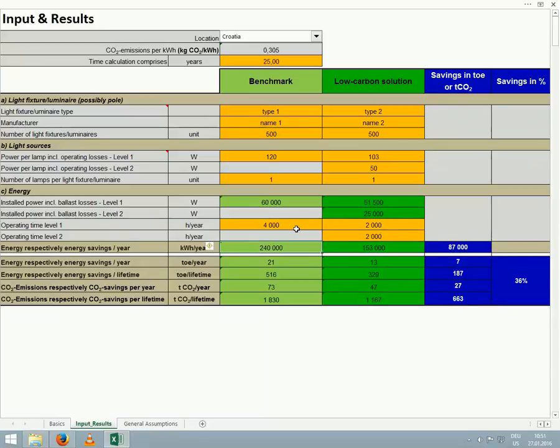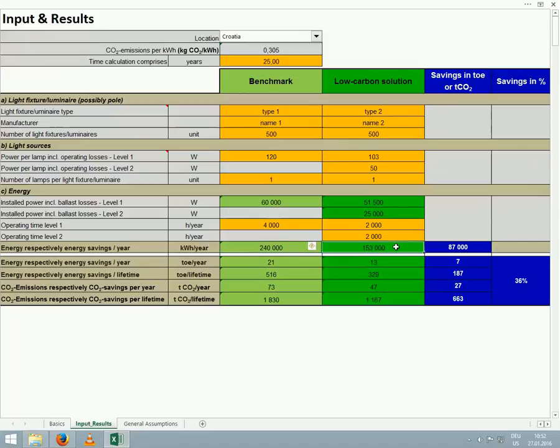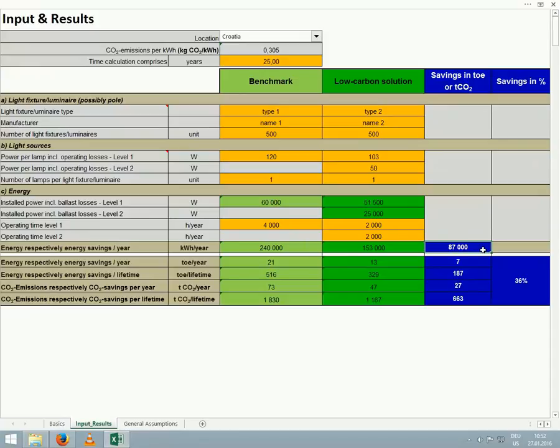Now we have entered all necessary information, and we can review the results for energy and emissions savings. We see the benchmark consumes 240,000 kilowatt hours per year, while the low carbon solution requires just 153,000. In this case, using the low carbon solution results in savings of 87,000 kilowatt hours per year.